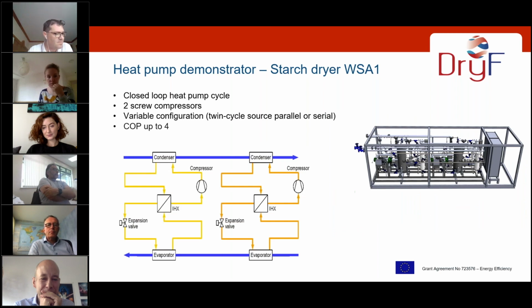On this slide, you can see the hydraulic scheme shown on the left-hand side. It's a twin cycle configuration with two screw compressors, with internal suction gas heat exchanger and evaporator connected in parallel, which also has the possibility to change to a serial configuration. This configuration has considerable advantages regarding safety, startup, and overall performance from very low to medium temperature lifts, which provides the highest COP up to approximately 4 at moderate temperature levels, with the highest energy cost savings per year.